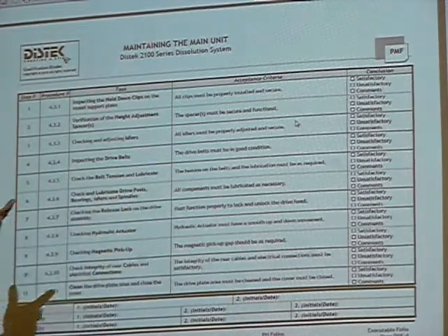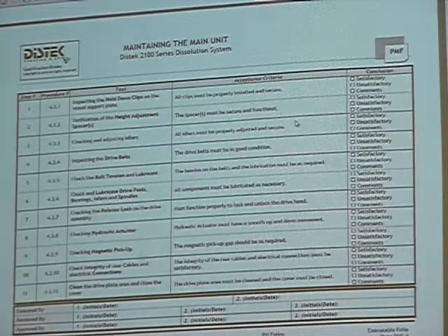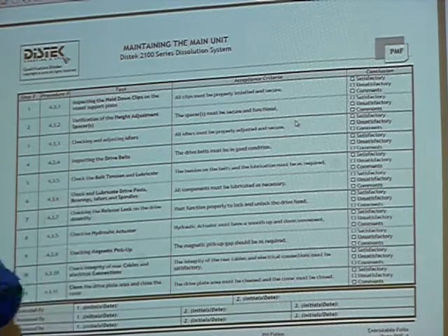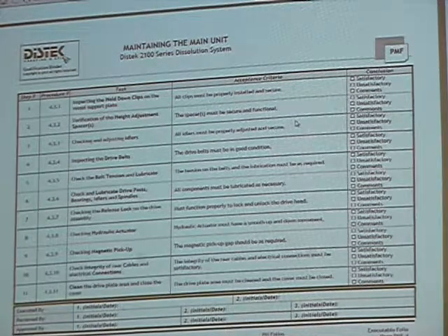Inspect the drive belts and make sure they're in good repair. You guys have worked on all kinds of baths. You know how belts look, how they have a tendency to crack. Make sure they're lubed properly. I put a thin layer of vacuum grease on the belt. I'll usually run it about 150 RPM.